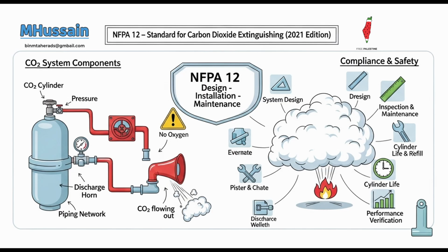How are flows calculated? For flow calculation, the design is based on average storage pressures: 300 psi, 2068 kPa, for low-pressure systems, and 750 psi, 5171 kPa, for high-pressure systems at 70 degrees F. Based on average pressure. The design nozzle pressures must meet minimums: not less than 150 psi, 1034 kPa, for low-pressure systems, and greater than or equal to 300 psi, 2068 kPa, for high-pressure systems. Minimum pressure at the nozzle. These minimums ensure sufficient force to propel the CO2 effectively into the hazard area.